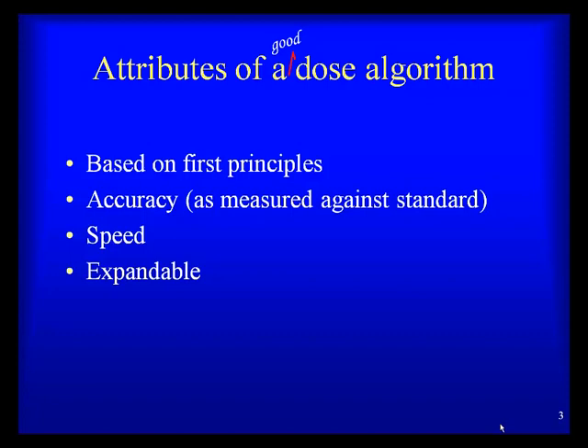What are the attributes of a good dose calculation algorithm? It needs to be based on first principles of physics. It needs to be accurate — accuracy is typically measured against measurements obtained in stylized phantoms, water or inhomogeneous phantoms. It needs to be fast because physicians and colleagues expect plans done quickly. It also needs to be expandable so new modalities like IMRT or VMAT can use the same algorithm.